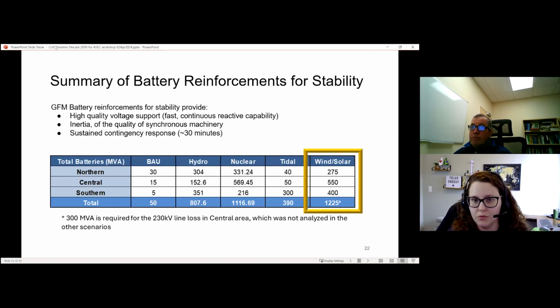Here is a summary, because we focused all the stability on the GFM batteries. The GFM batteries are nice for stability because they not only provide a fast response and help with the inertia issue we mentioned, but also have really good quality for voltage support, since it's a fast support with the capability to give continuous reactive power. Also, in the case of a contingency, it's able to sustain the response for a good amount of time. Here we have a comparison for all scenarios.